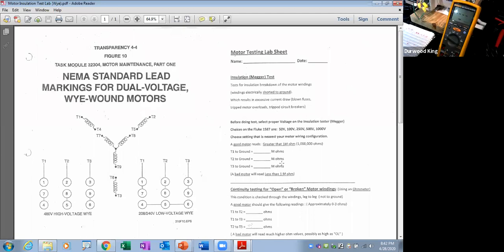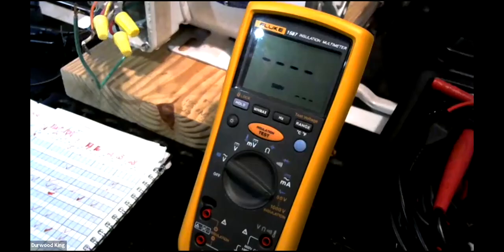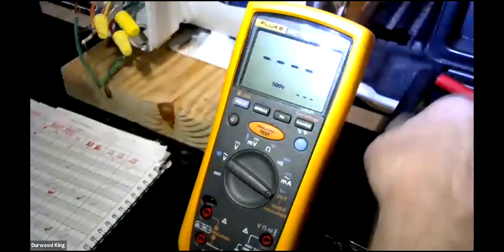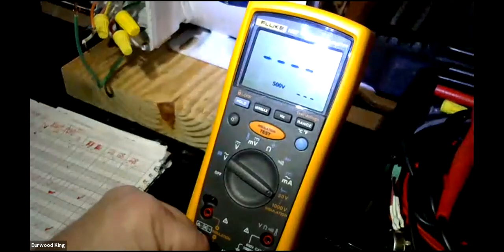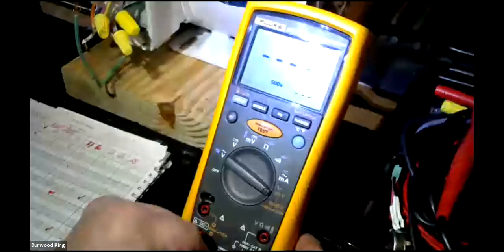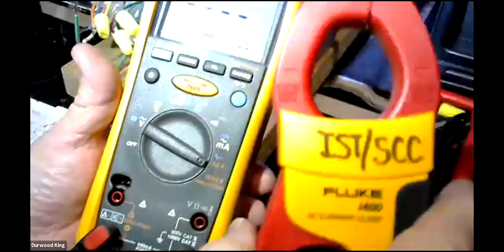Okay, so let's go. Turn the screen share off, and this meter comes out of a kit with a lot of leads in there. Now, this meter can also read amps. Okay, so it has the jacks here. If I wanted to use this meter checking amps, then basically what I do, I take that amp clamp and go down here to common here, and milliamps. And for every amp that it reads, it converts it into 1 milliamp.